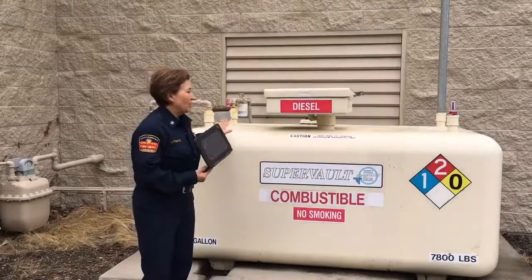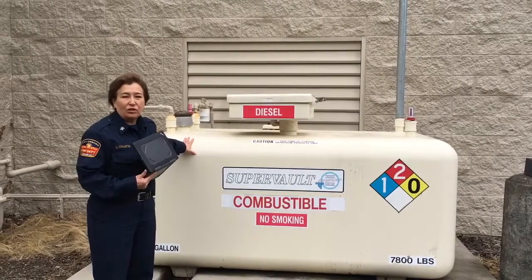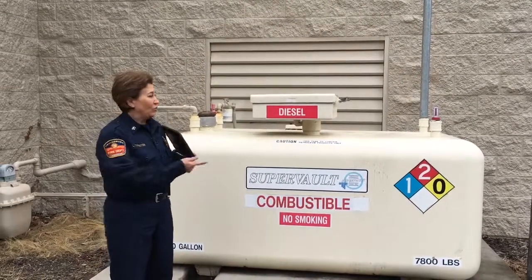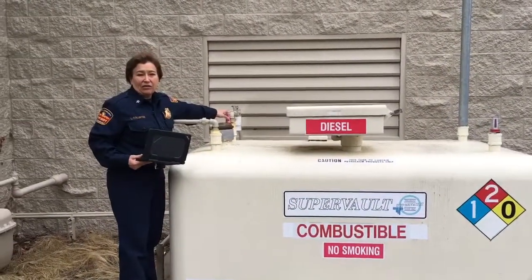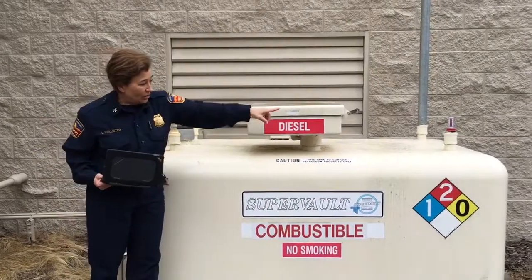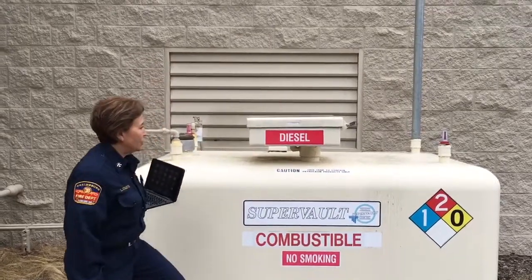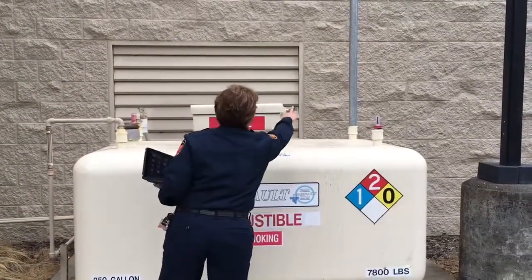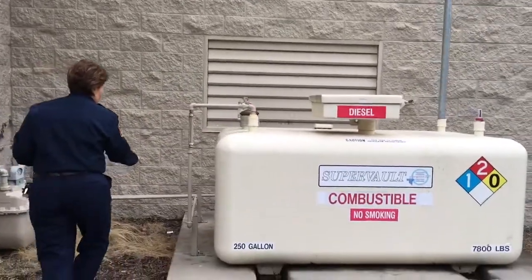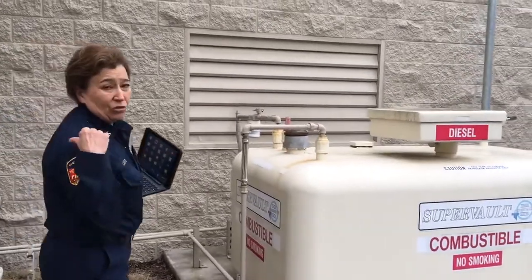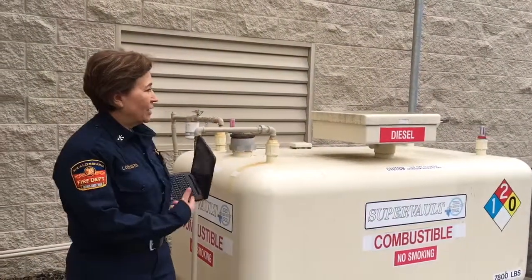Okay, so we have our above ground storage tank here. It's 250 gallons, and it feeds our diesel generator. So just like I said, they do weekly inspections on this. We have a leak alert, which is over here, so it checks the secondary to make sure. They make sure that we have a proper amount of fuel in here and that we don't overfill it. And this can is locked as well, so people can't steal it. We got the vent, and then we also have the piping over here. So he comes and checks to make sure that the piping is all secure and that there's no leaks. So that's the only other material I have.